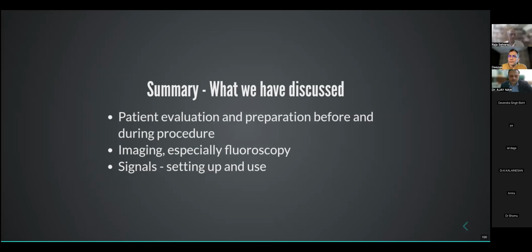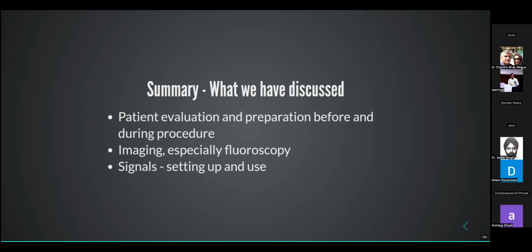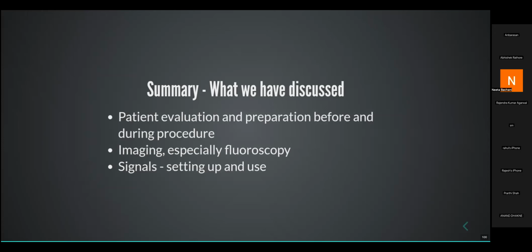Yeah, it's a very pertinent question because it's not discussed otherwise in textbooks, but it's a practical issue that we face every day. So definitely, if there is noise and you've eliminated other sources, if your catheter is used multiple times, it's better to change it. It's preferable to have a tab on how often you're reusing a catheter and have a limited number of reuses. And with an ablation catheter, what we find is sometimes deflection breaks, sometimes the thermistor doesn't work, so your temperature doesn't work. Not sure you usually end up with ineffective ablation just because of reuse.